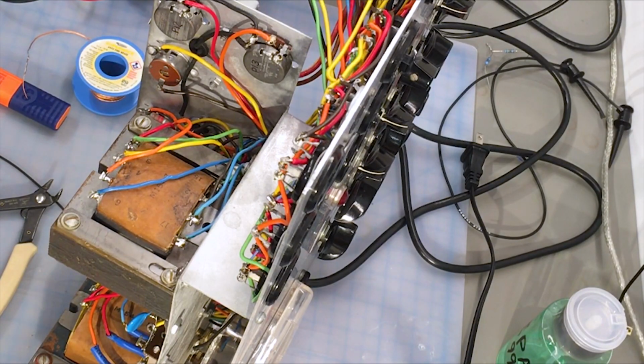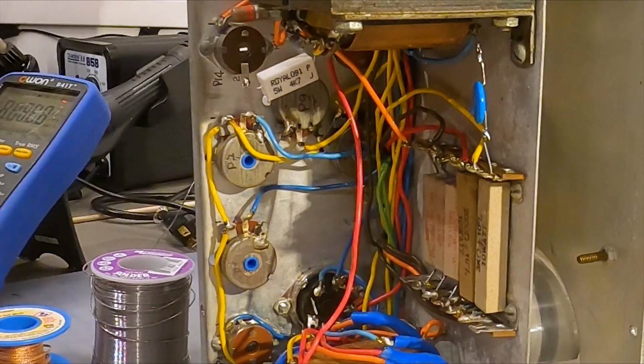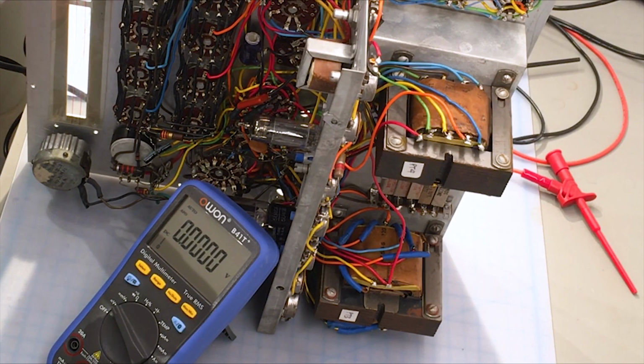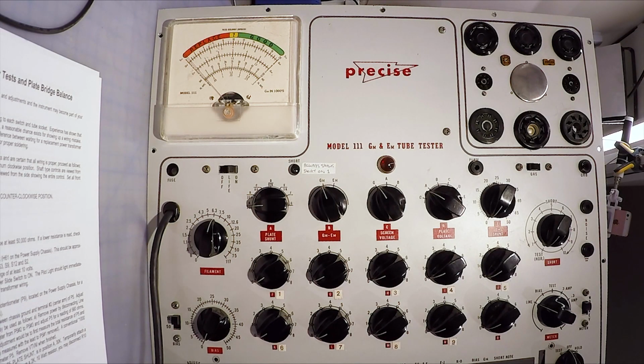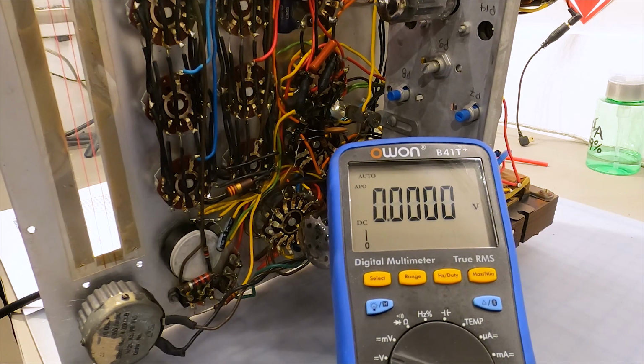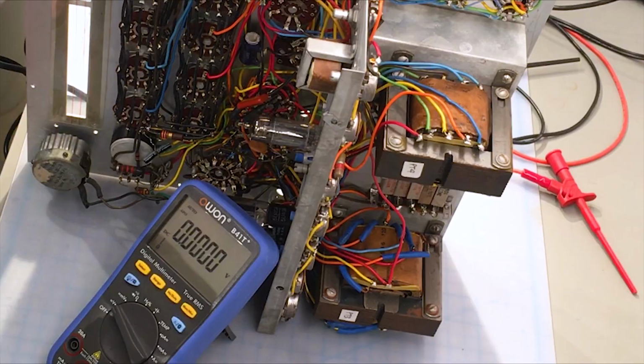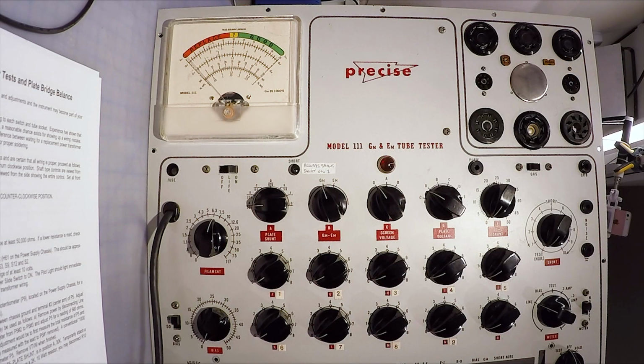Okay. Are both of these operations complete? Well, what we have here is the Precise Model 111 tube tester on the bench, tipped on its side, and I've changed the electrolytic capacitors, reconnected a detached resistor, and gone through and changed one or two out-of-specification resistors, and checked the pilot lights and indicator lights to make sure that there is conductivity so that we're not misled by any failure of these lights to illuminate properly. And we're about to go through the calibration instructions and make sure that the unit is working properly.